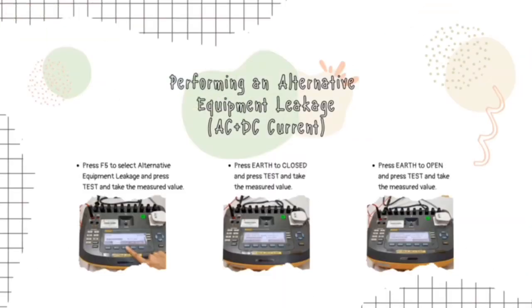For the next is performing an alternative equipment leakage AC plus DC current. First, press F5 to select alternative equipment leakage and press test and take the measured value. Press earth to close and press test to take the value. Then press earth to open and press test and take the measured value.